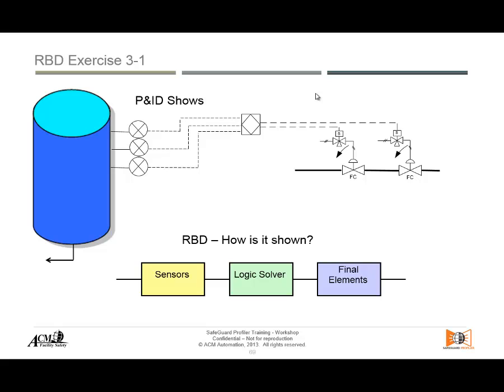The sensor is in series with the logic solver, which is in series with the final elements. This means we need the sensors to work, the logic solver to work, and the final elements to work — all of them — in order to have success. This is different from the fault tree, where the thinking is always the opposite from the reliability block diagram.